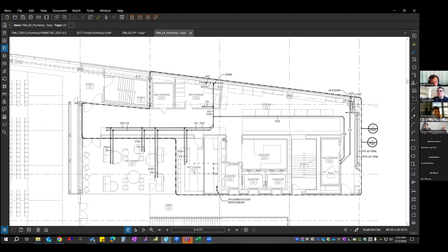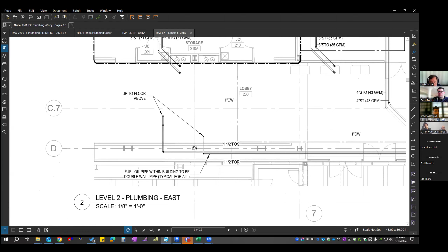Up here we have a roof above this, the mechanical well, so a lot of this is shown here, including the storm serving this area. We show our fuel oil system exiting here, routing tight, and then going up to the generator on the floor above. We show this fuel pipe as double wall anytime it's within the building and not in a rated chase.